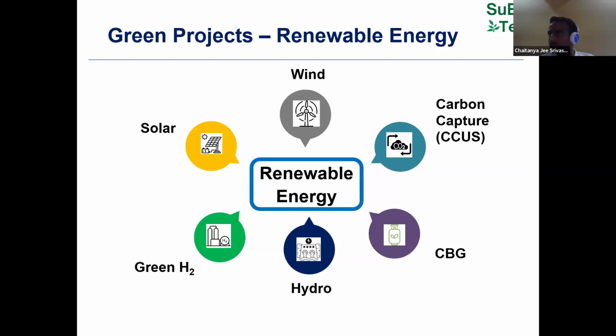So solar power projects are of two types: rooftop and ground mounted. Ground mounted means, like any power plant, it requires land. Ground mounted solar requires roughly 3 to 3.5 acres for 1 megawatt of solar. The capex will be around 4 crore per megawatt. These projects are basically megawatt-size projects, with a transformer, and like any power plant, it is connected to the grid.